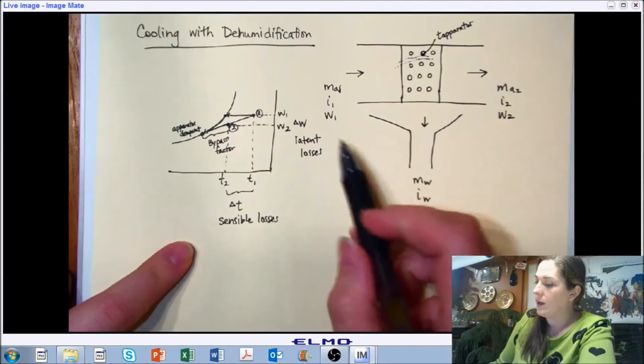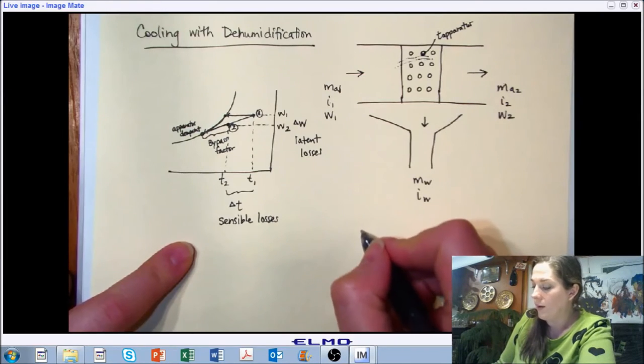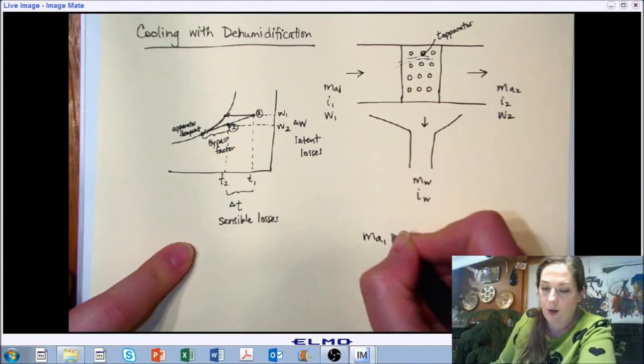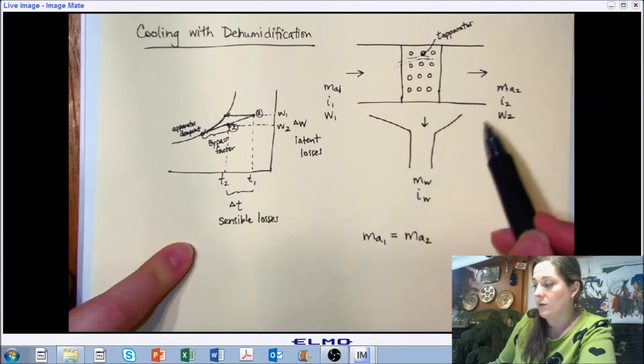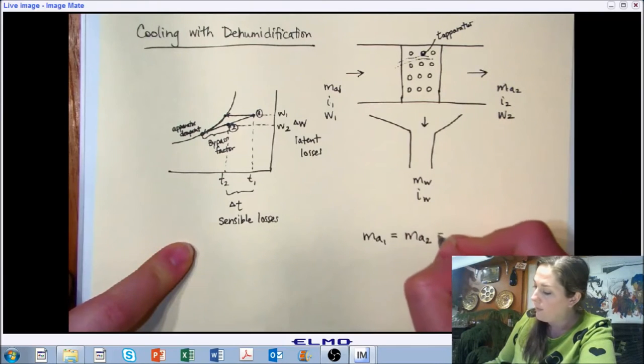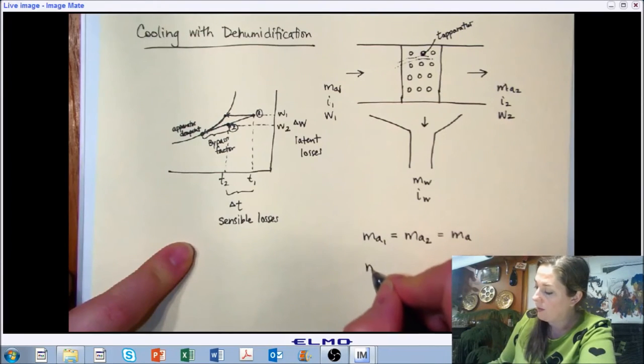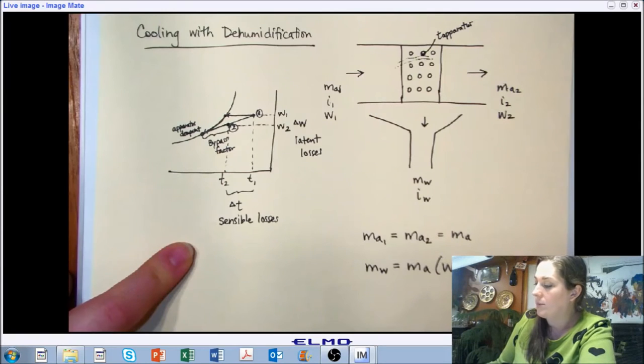When we think about our inlet, our outlet, and our moisture, we still have to think about conservation of energy, conservation of mass. Our mass of air is the same for both. The properties of the air have changed, but we still have the same amount of air coming in and leaving. But now, we have removed some of the moisture. The amount of moisture that we removed is related to the amount of air times the change in the humidity ratio or the absolute moisture of that air.